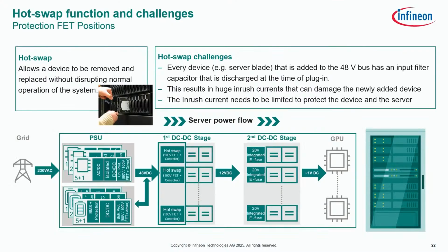Every time a device, for instance a server blade, is added, it has an input filter capacitor that is discharged at the time of plug-in. This results in a really high inrush current, and potentially some failures in the systems can be observed. That's why our MOSFETs, or in general MOSFETs placed as a hot swap MOSFET, need to be able to handle high inrush currents so that this risk of potential failure does not occur. Our MOSFET is located between the back plane, in the direct current plane of the back plane, and the load. That's why low ohmic devices are super crucial here.